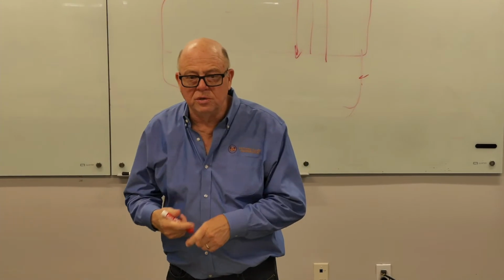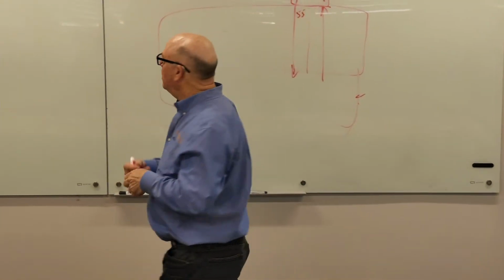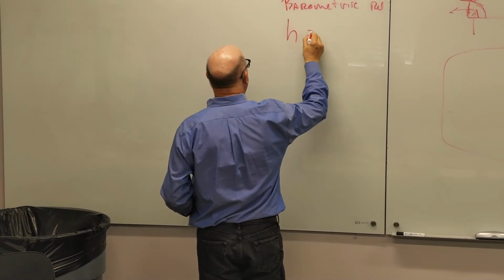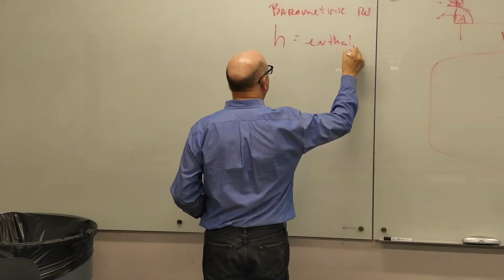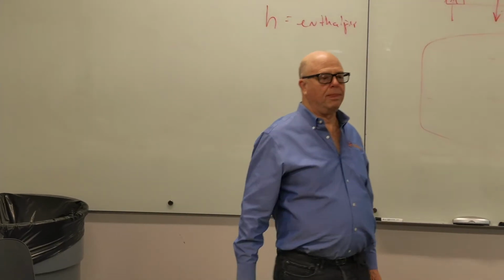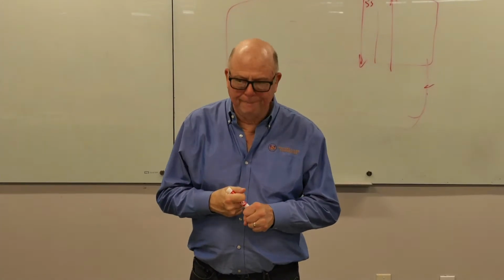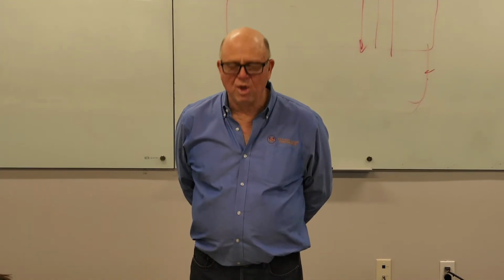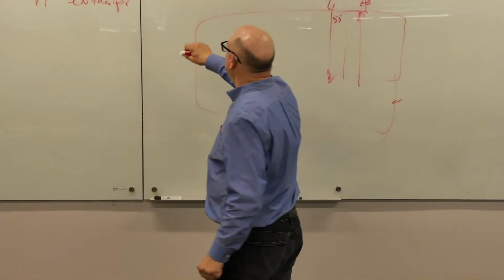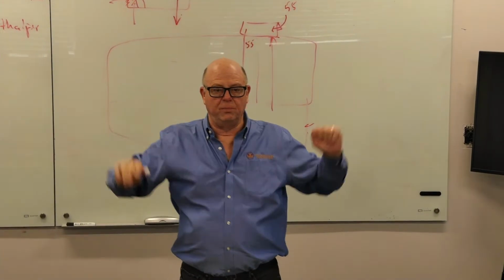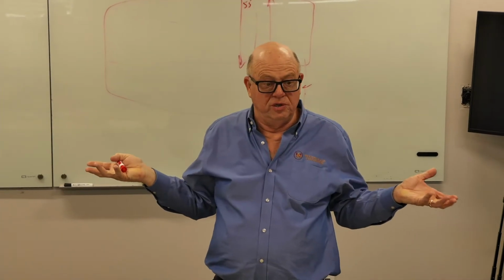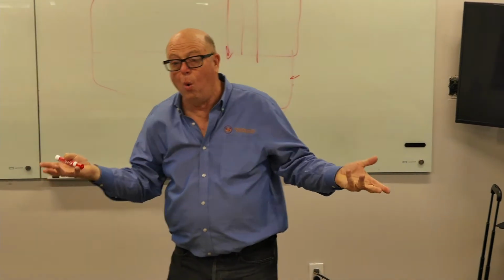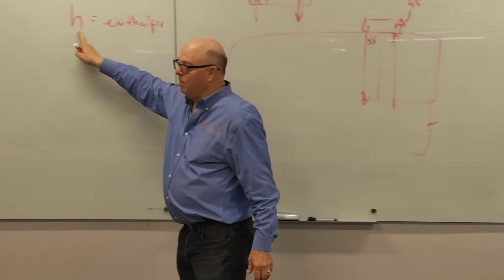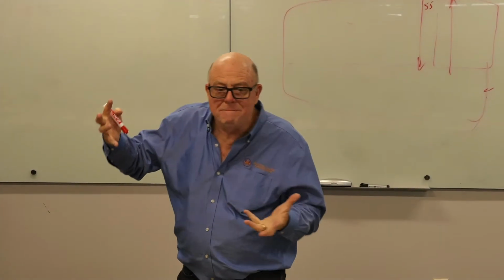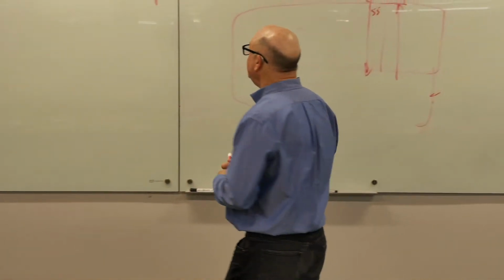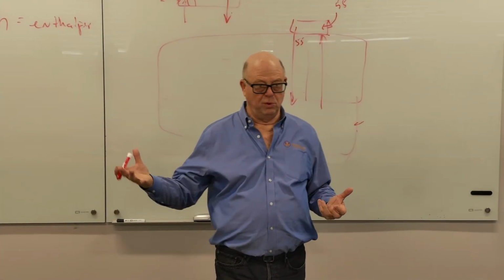So then the next step was, we haven't done psychrometrics yet, but there is a little symbol, a little h, which stands for enthalpy. What is enthalpy? It's a measurement of energy. It's how much energy there is in the total air. See, this is sensible heat, what you'd see on the thermometer. It has no idea what the latent situation is. Is it dry as heck or is it raining? It doesn't know. But the enthalpy, if you measure the enthalpy, that is the mix of sensible and latent heat, latent having to do with the moisture in the air.